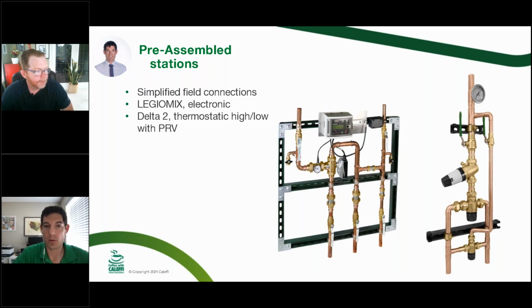Yeah, so these are both single product part numbers from Caleffi that we can send, mounted on the unistrut like that. That would be the LEGIOMIX in the center with the proper recirc piping with the check valves in the right places. You could just press right onto that with your recirc line, select your recirc pump correctly, and you're good to go. One of the questions we had before the class was about certain jurisdictions requiring a pre-assembled skid, so that would be a good way to go.